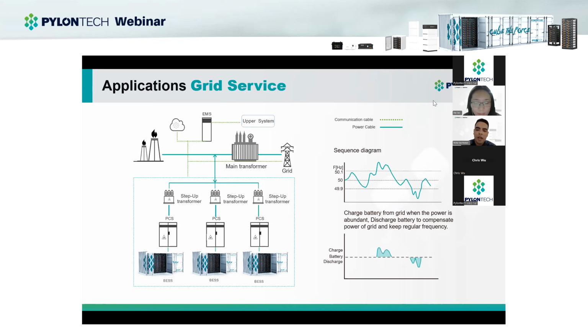It can go up or down in terms of frequency. So what the battery will do is charge when the grid is abundant, when we have plenty of energy, and it will be waiting until the grid has low voltage or low frequency. Then immediately the PCS will discharge the battery. It will go to a step-up transformer if needed, since the voltage from the PCS might not be the exact same as the grid, so it may need to step up or step down, but it will discharge the batteries and send that to the grid.